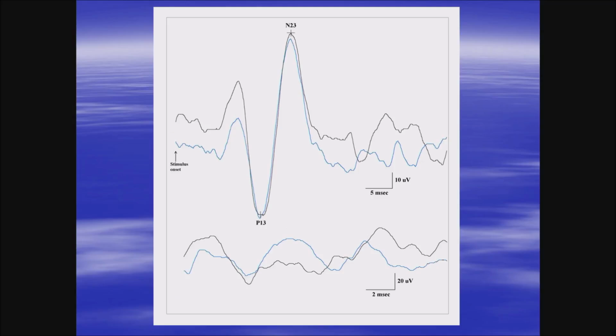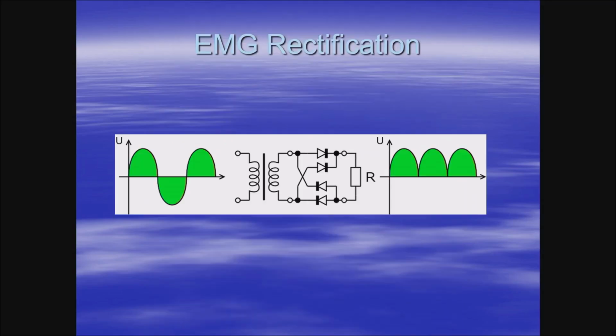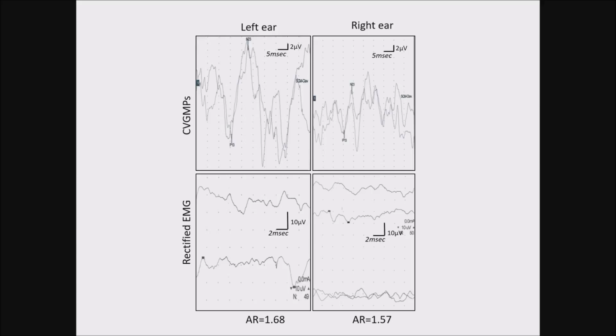if you don't have such a software program, you can use the sensory nerve conduction study on your system to record the muscle activation. I say the sensory nerve conduction study because what you are recording is in microvolts, and your motor nerve conduction study will not be sensitive enough to record this. So you need the sensory nerve conduction study program, if you have it, to record the EMG in the microvolt range and measure the amplitude and compare it to your CVEMP, so you have a definite amplitude parameter for each patient. And why is it important to record EMG?